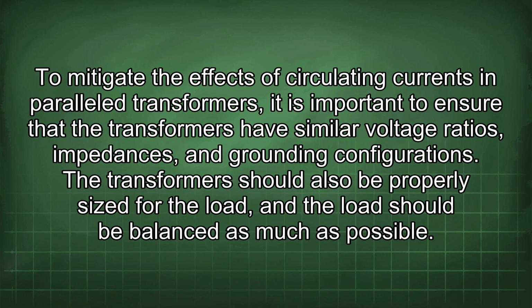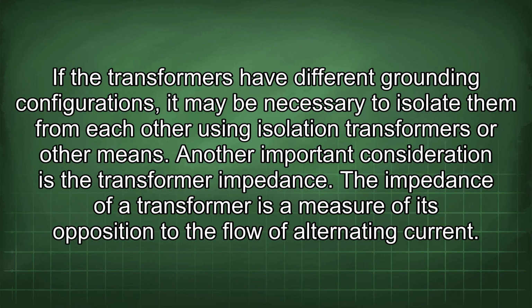lifespan. To mitigate the effects of circulating currents in parallel transformers, it is important to ensure that the transformers have similar voltage ratios, impedances, and grounding configurations. The transformer should also be properly sized for the load, and the load should be balanced as much as possible. If the transformers have different grounding configurations, it may be necessary to isolate them from each other using isolation transformers or other means. Another important consideration is the transformer impedance.